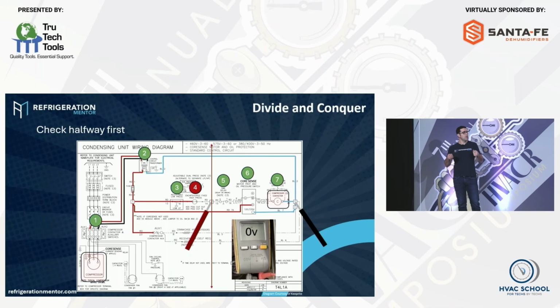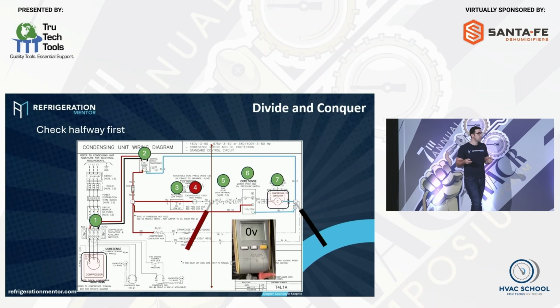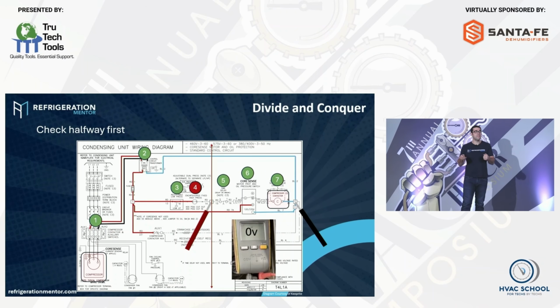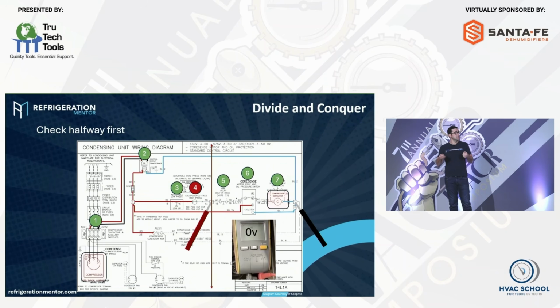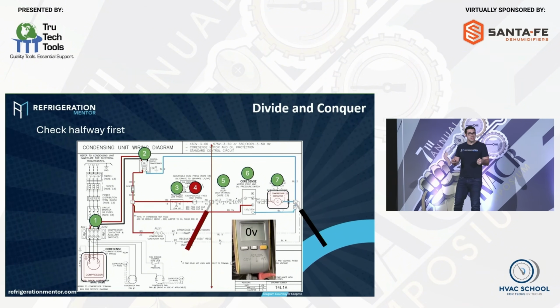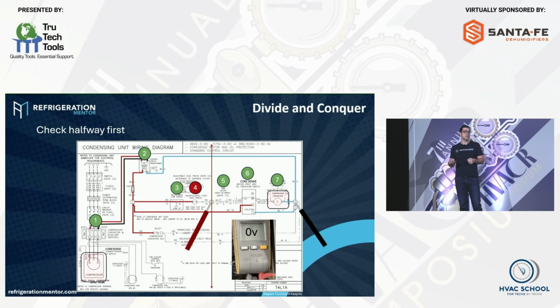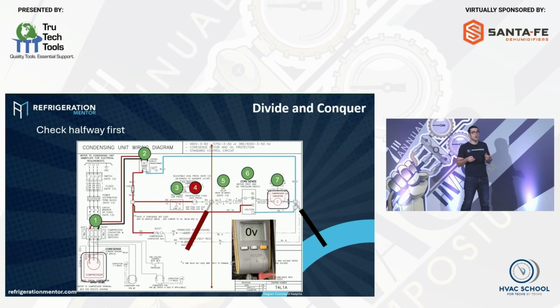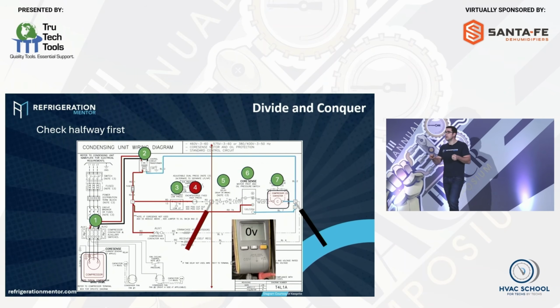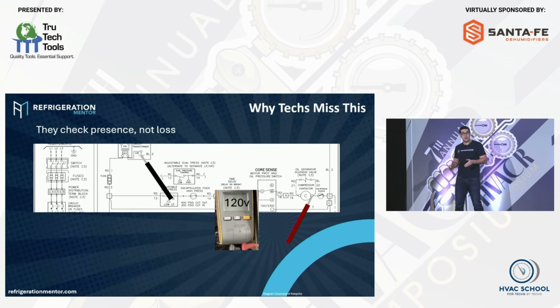Divide and conquer. So if I went from this point here to my common or my N, I'm in the middle. If I have no voltage there, what does that mean? That means something before it, something upstream, is open. Now, if I do have voltage there, that means something downstream is open after it. Does that make sense? Now we really want to understand how to use that meter, and we can break our troubleshooting up a lot quicker.